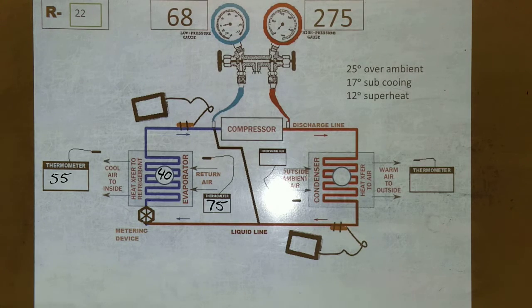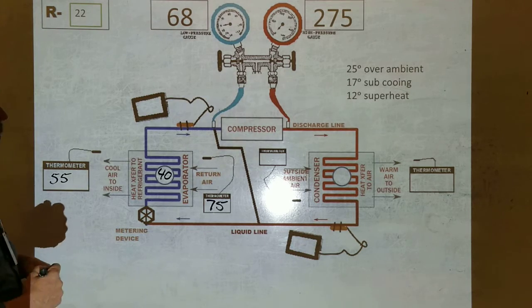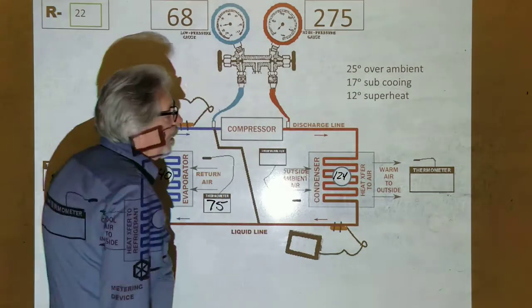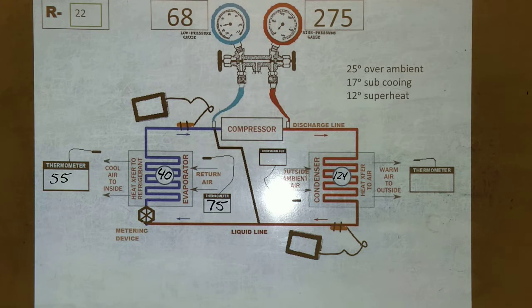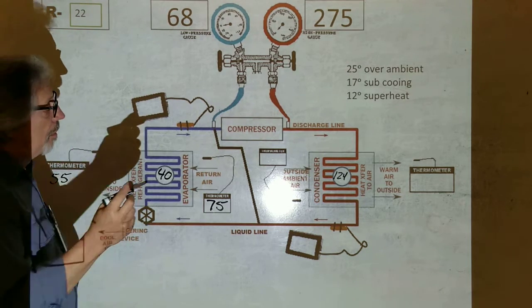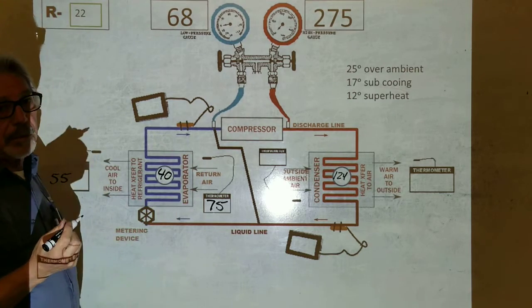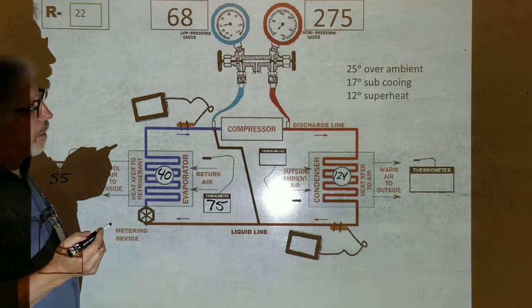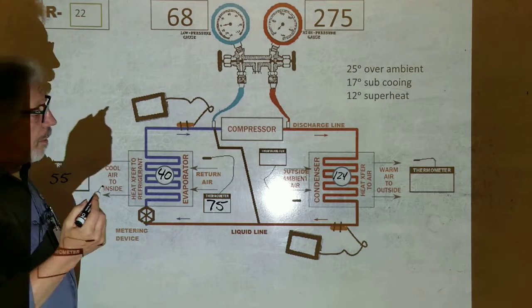Okay, so this side right here is 275, which is what? 130? 124. 124 degrees. Okay, and assuming we got 25 degrees over ambient, 99. That is an awful picture, Marco. It's 89? I believe so, double check. 89 or 99? No, it's a 25 degree difference. Oh yeah, then my 99 is right. It's 99 degrees.